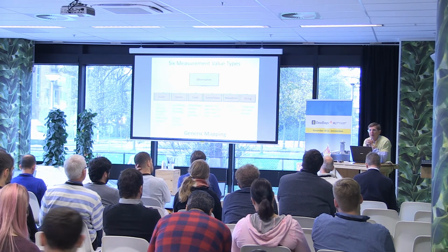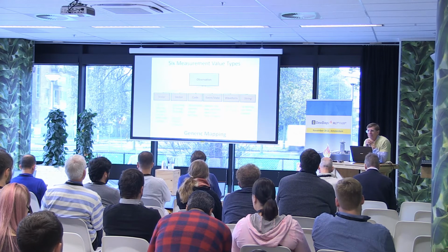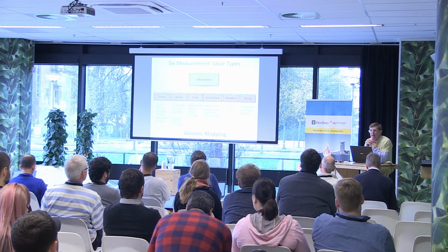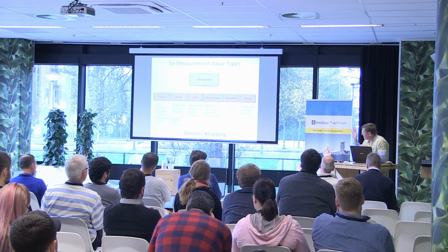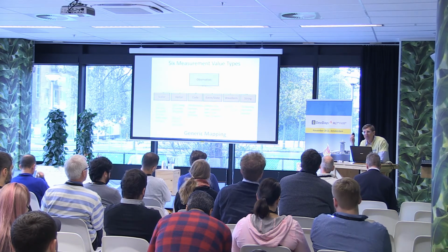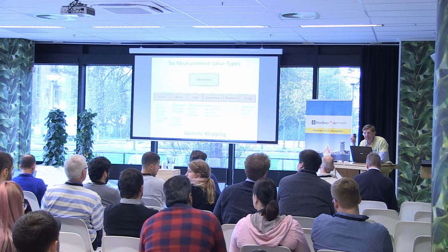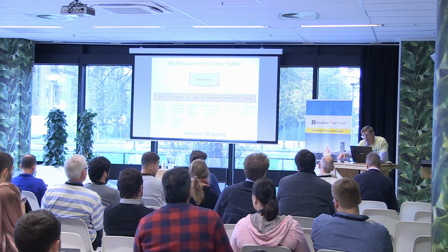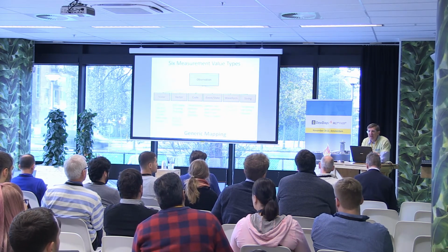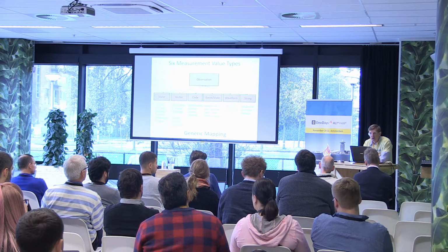So thank you. And a follow-up, there's another code on each observation, which is what identifies the observation. Yes, exactly. Where does that come from? That also, everything that this profile talks about, comes from the device. So the device knows the LOINC code for what it's meant? It's not the LOINC code. This uses the IEEE 11073 10101 codes, nomenclature codes.